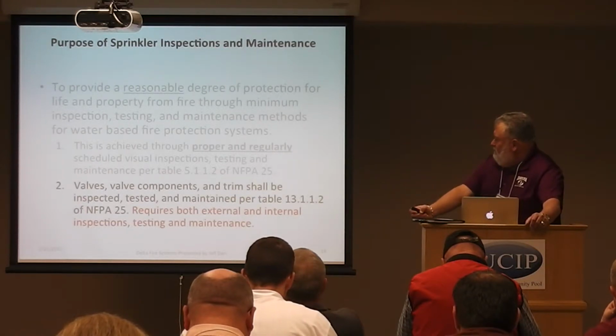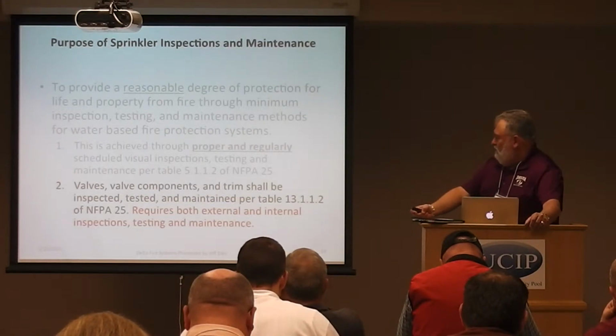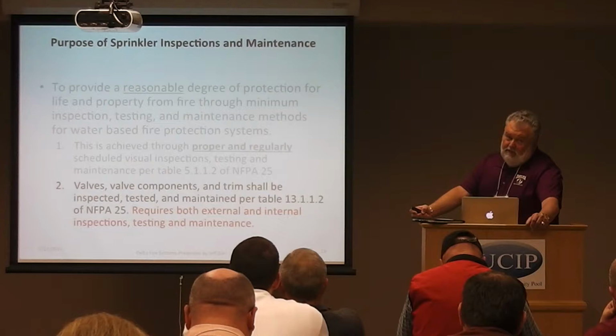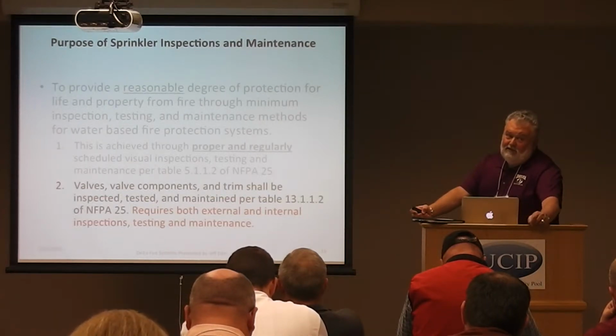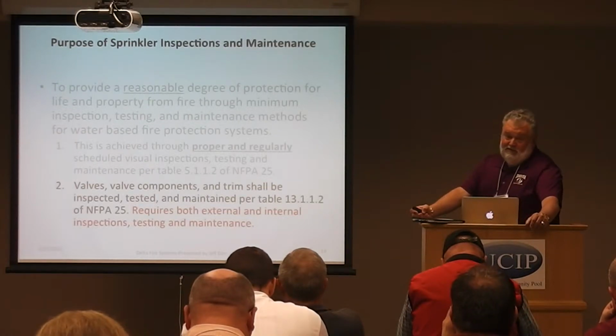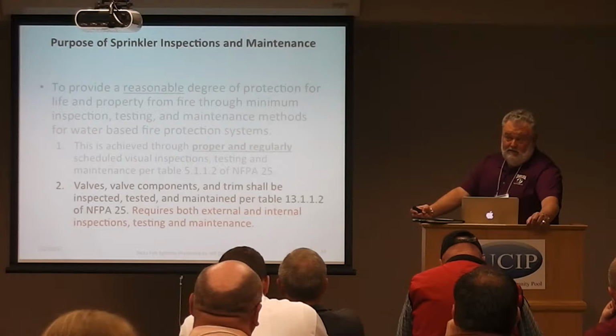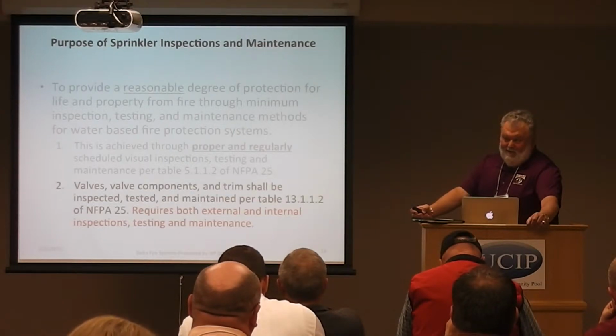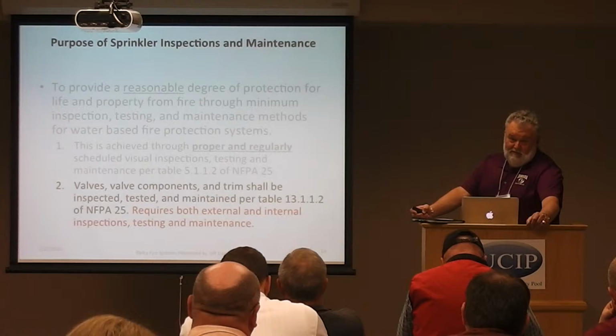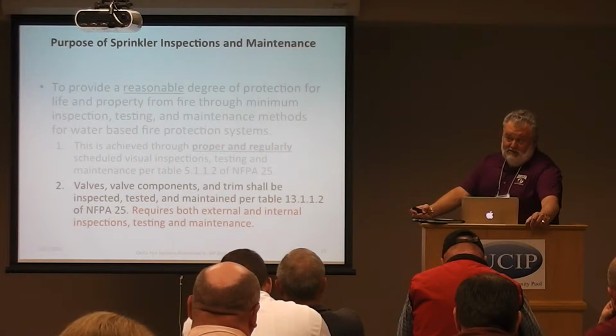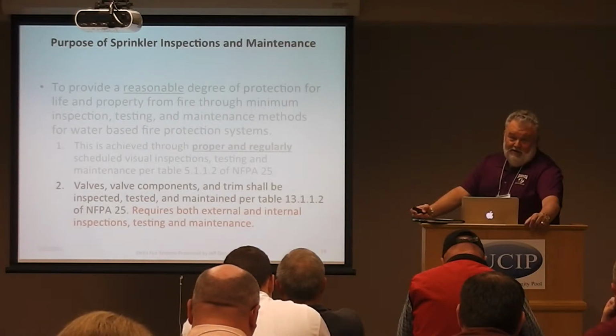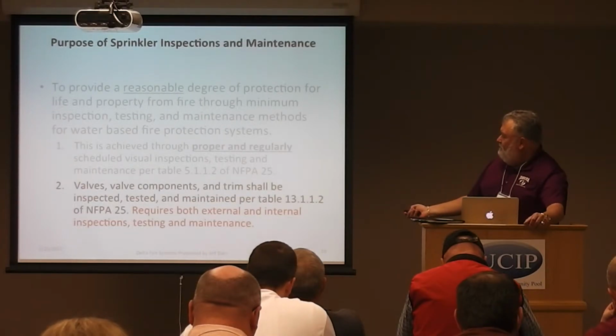The valve components and trim shall be inspected, tested, and maintained per table 13.1.1.2. This table requires both an external and an internal inspection of the valves. I've seen some of our competitors tell customers that you don't have to do an internal inspection. And, very clearly, all they're doing is what we call in the business rag tagging. And they're not doing you as the customer any favors at all. They're charging you just to come in and sign the tag and put it on your riser. So be cautious of that.